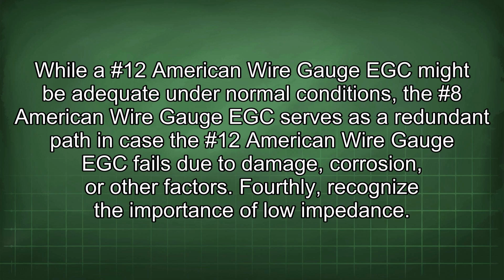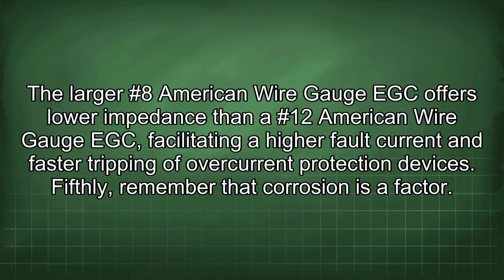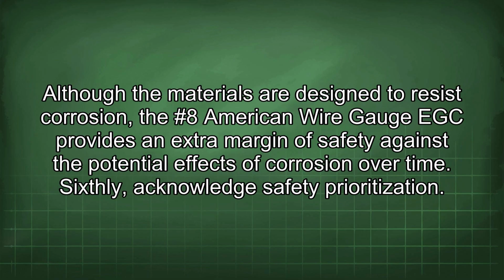Fourthly, recognize the importance of low impedance. The larger #8 American wire gauge EGC offers lower impedance than a #12 American wire gauge EGC, facilitating a higher fault current and faster tripping of overcurrent protection devices. Fifthly, remember that corrosion is a factor. Although the materials are designed to resist corrosion, the #8 American wire gauge EGC provides an extra margin of safety against the potential effects of corrosion over time.